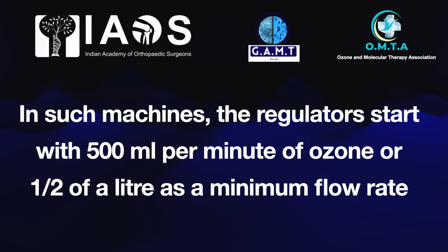In such machines, the regulators start with 500 ml per minute of ozone, or 500 ml of oxygen, or half a liter as a minimum flow rate. At half a liter of oxygen at 40 micrograms per ml of ozone, it is a totally unsuitable machine for EBOO.